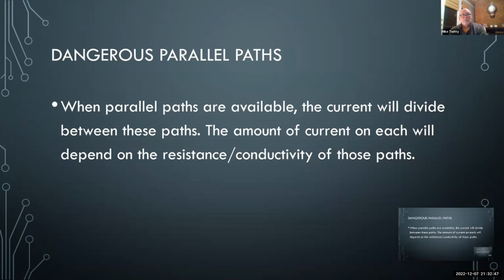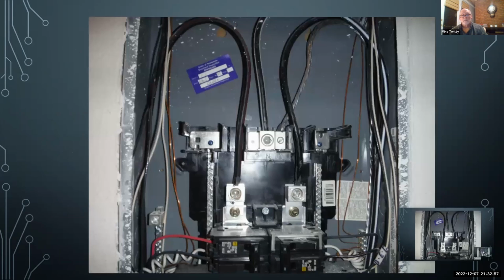Okay, when parallel paths are available, it'll divide between these paths. And depending on the resistance and conductivity of those paths is how much goes on each one. Now, look at this one. This is a sub panel in a house. Just kind of look at it like you're doing an inspection. Does anything jump out at you other than the state of Tennessee approved code inspection? He said everything was good here.